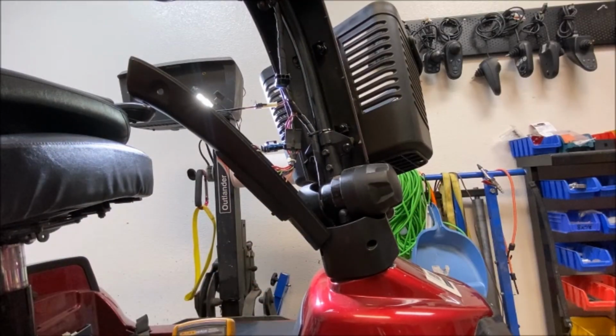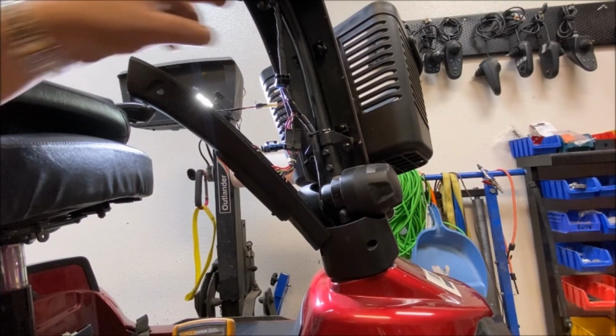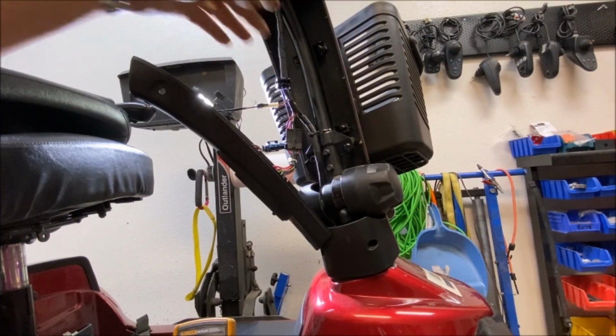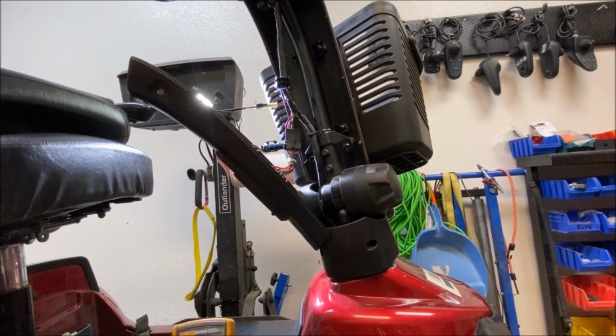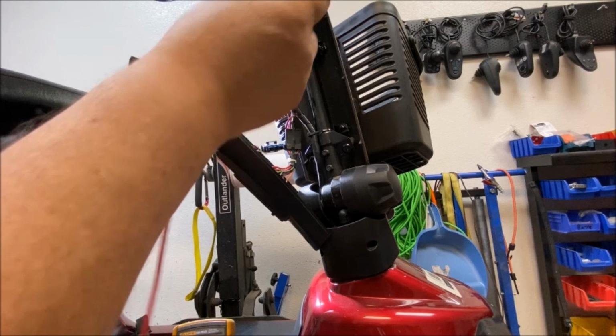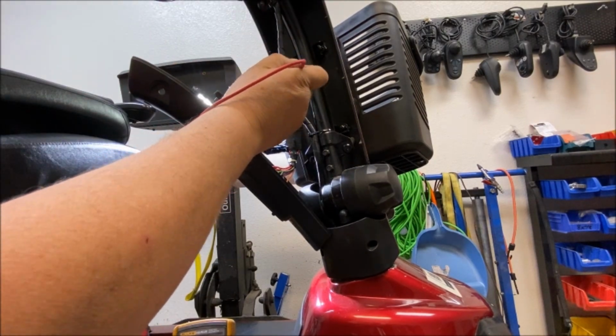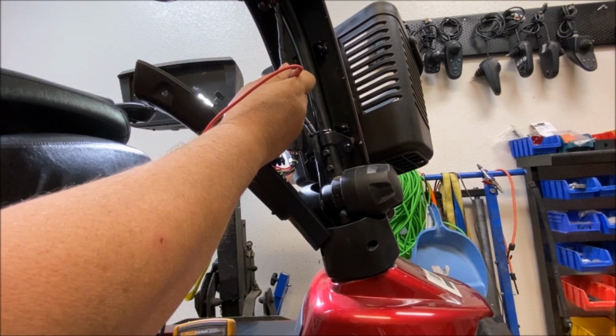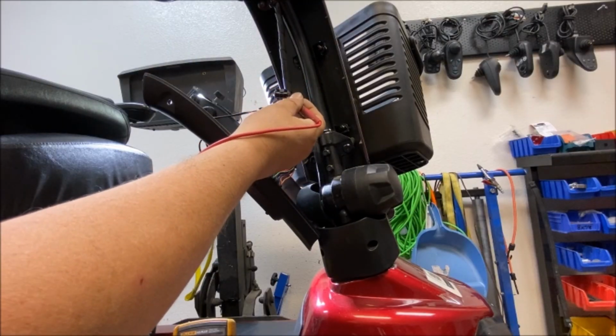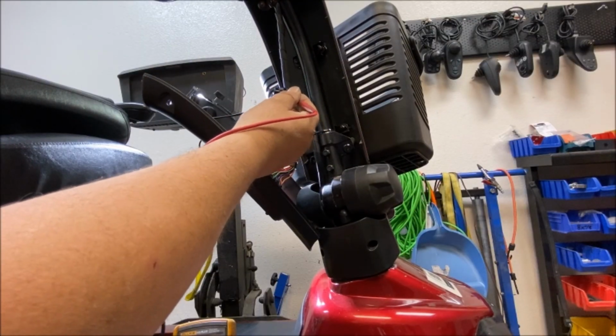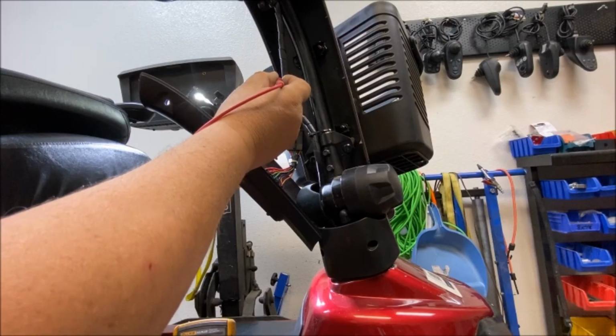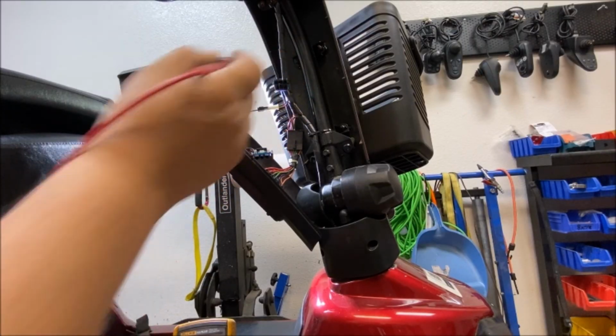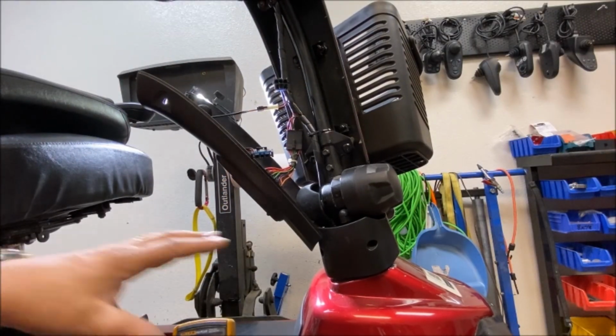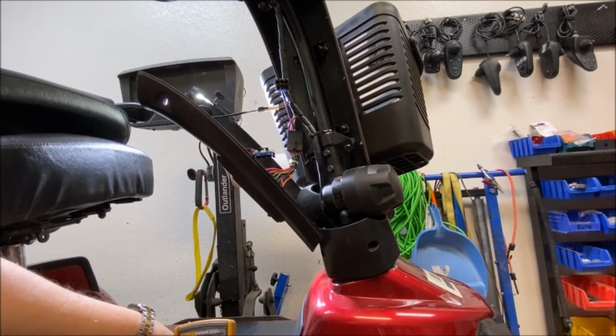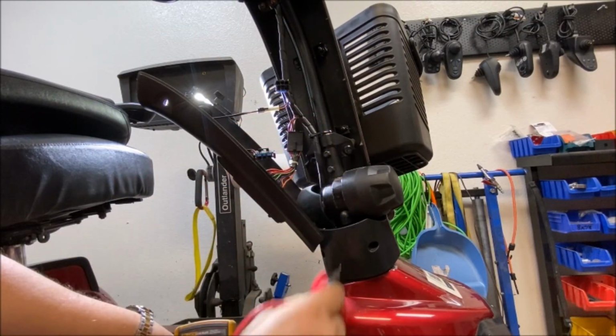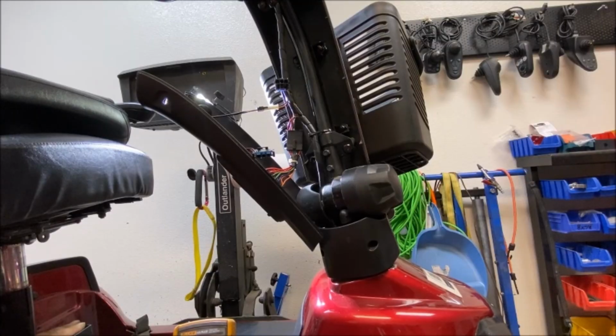That's fine. The next thing you would do is test the other plug to the tower. Again, we should have continuity on some line. If we don't have it, then we know we have a problem. So we have an audible beep there for the positive, and then the negative again, so we know that wiring is fine through to that circuit, ruling out any break in this cable to the tower.